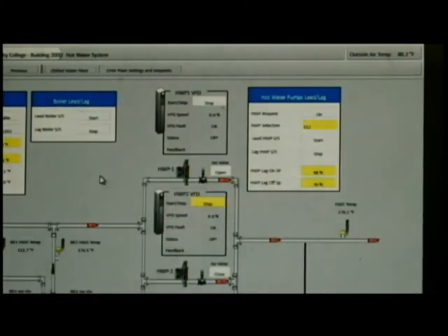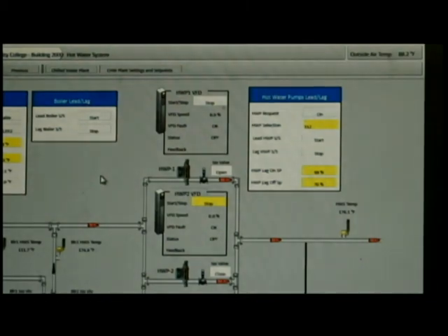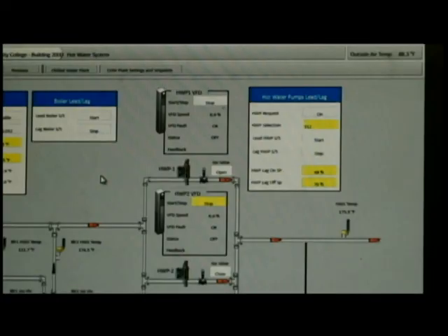So what that means is if our lead pump gets to 98% or above as far as VFD output, then we are assuming that we need more flow out in the system. So what we do is start a timer, which is adjustable, for a couple minutes to make sure that we don't cycle the lag pump on and off. Then we bring on the lag pump, whatever is chosen via the hot water pump selection at the top of the panel right there. So right now, lead pump is number three. It's running along. If it were to get to 98% or above and stay there for a couple minutes, then we would bring on hot water pump number one. And when that happens, its ISO valve opens up, then that pump will start to run. And then the two pumps will run in tandem at the same VFD output or speed. So as soon as one comes up, then one and three now speed will match each other and maintain that 10 PSI set point out in the hot water loop.